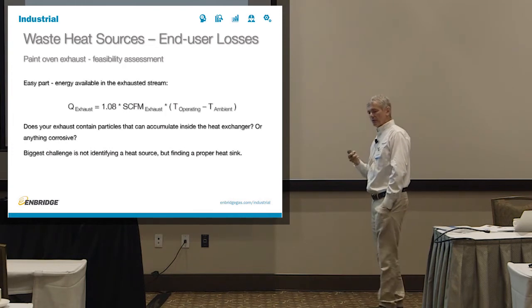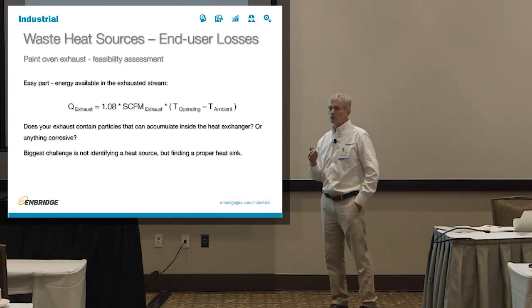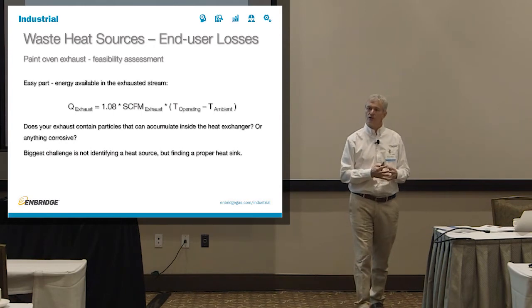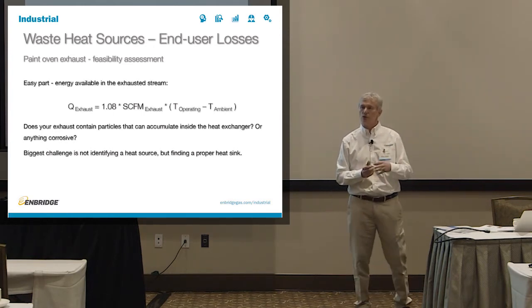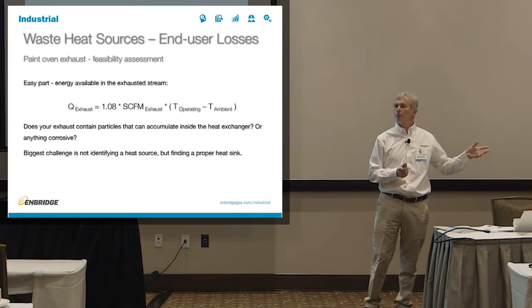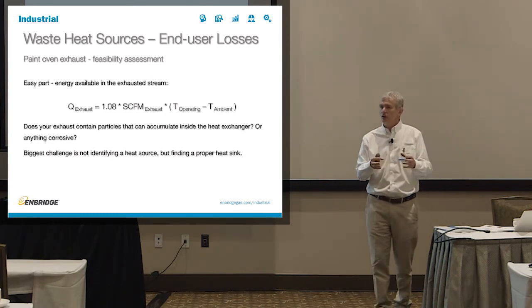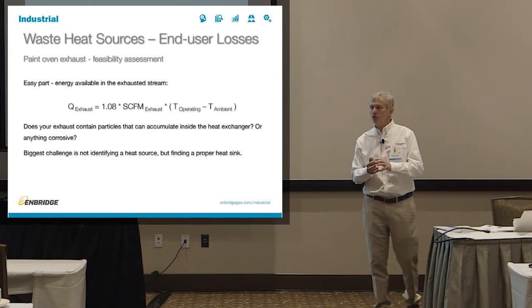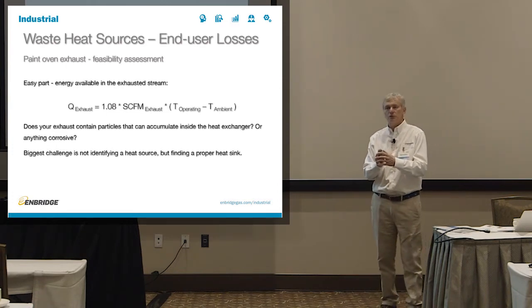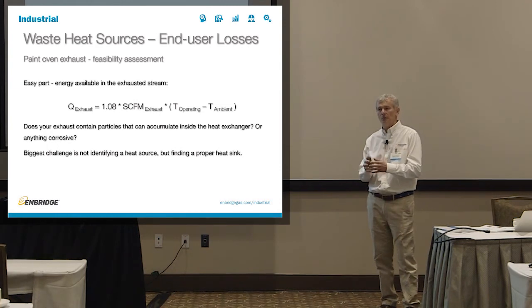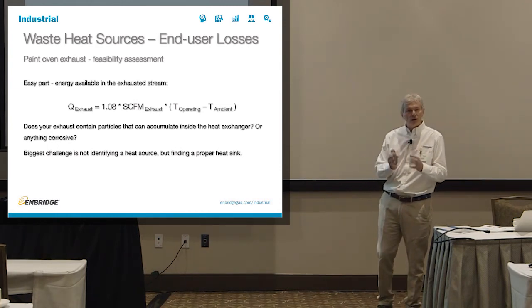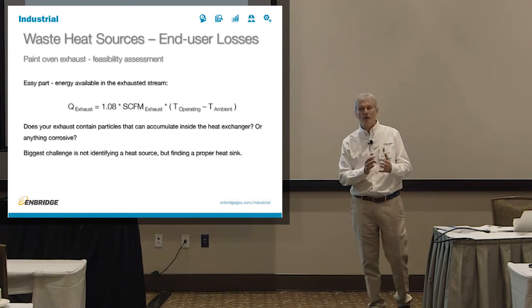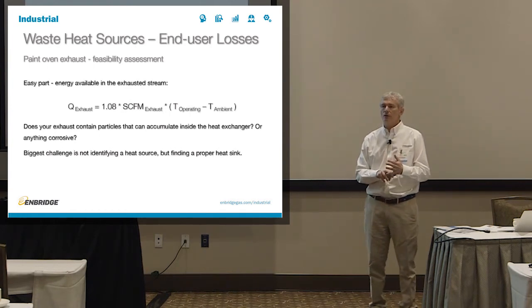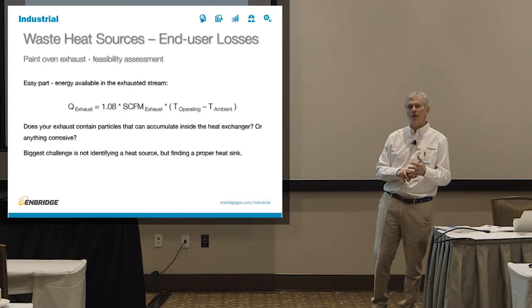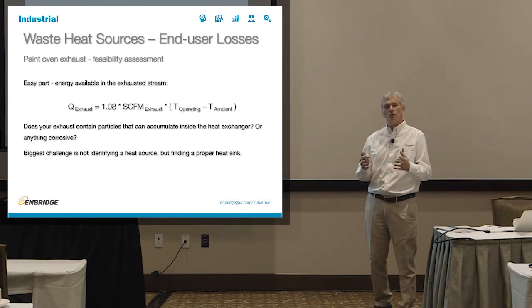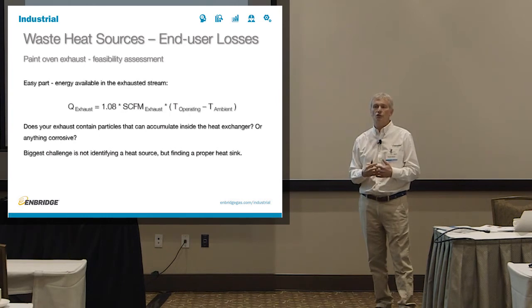The thing that people get very confused about is what's in the exhaust. You have to know what's in your exhaust if you're going to recover it. This is not something you can just put back into the facility, like a little compressor, because this is actual exhaust. So you can only do an air-to-air heat exchanger or an air-to-water heat exchanger. You have to do some sort of heat exchange. You cannot use it as is. If you've never used a heat exchanger with the airflow, you need to know what's in it. Is there something corrosive? Are there big particles in there? You need to know that because that will define what kind of heat exchanger you can actually have.